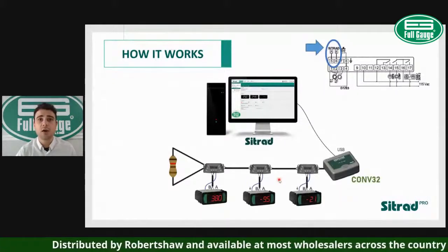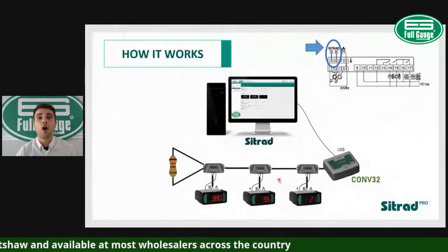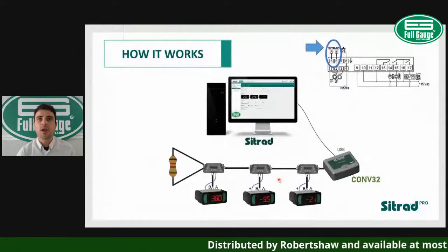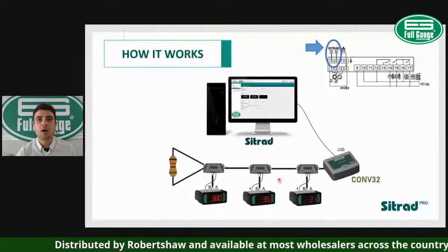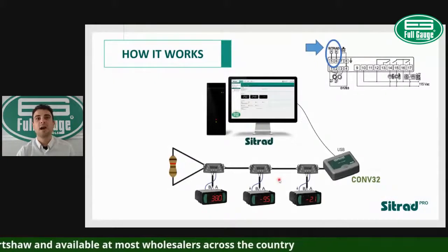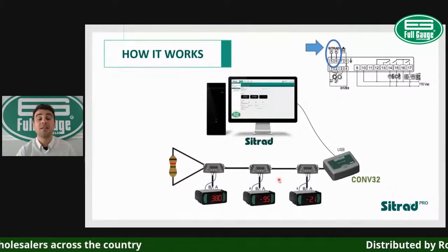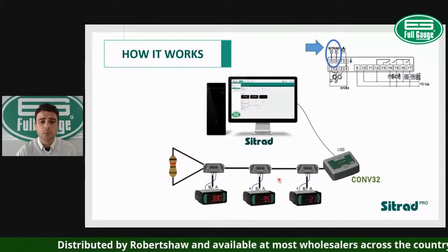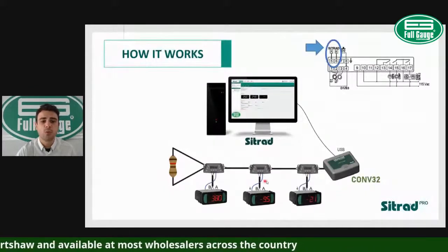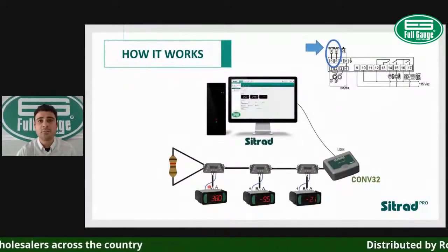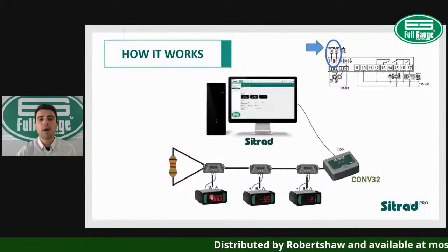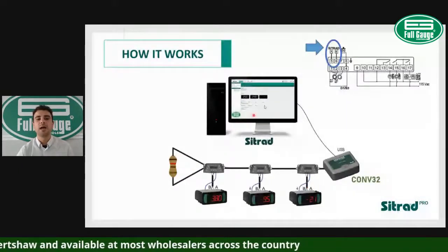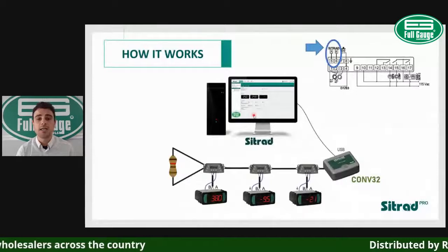You change the serial address; it is always the last parameter of your Sitrad compatible controllers, the serial address within the 485 network. So once we assign unique addresses, for example, address 1, address 2, address 3, and so on, my Sitrad software can easily recognize every controller connected to my Sitrad network.